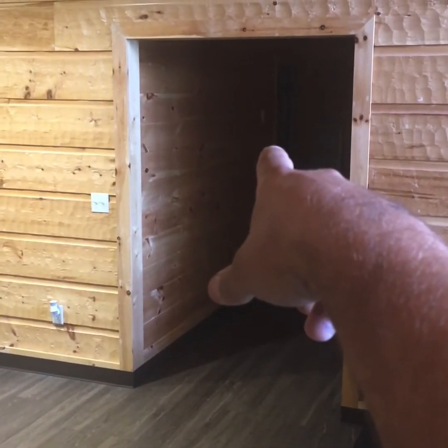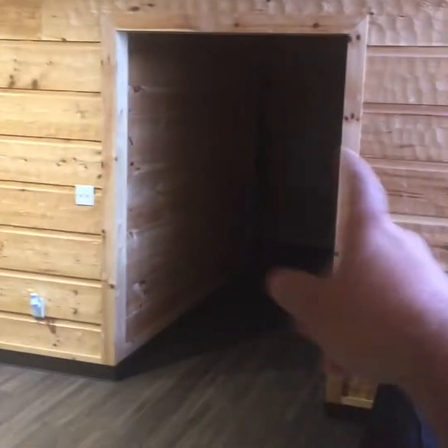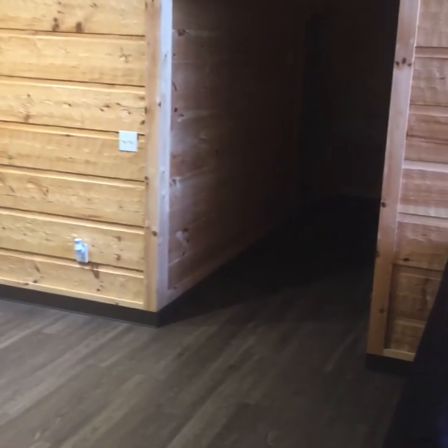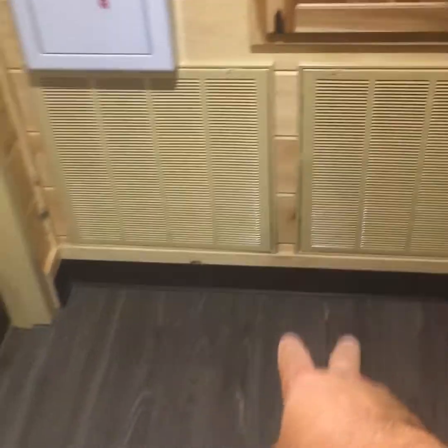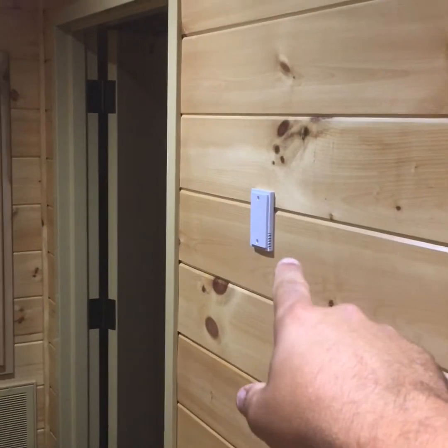never kicks on. So I currently have the units programmed to automatically circulate air every 30 minutes of every hour, I think, or 20 minutes of the hour. And then you have transfer vents, so even if these doors are closed, it will move air through the bunk space into the primary returns. There are large 4-inch media filters under the floor that need to be changed out. But that's one of the issues.